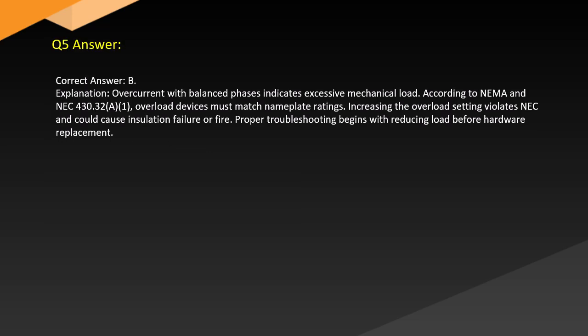Answer. Correct answer: B. Explanation. Overcurrent with balanced phases indicates excessive mechanical load. According to NEMA and NEC 430.32(A)(1), overload devices must match nameplate ratings. Increasing the overload setting violates NEC and could cause insulation failure or fire. Proper troubleshooting begins with reducing load before hardware replacement.